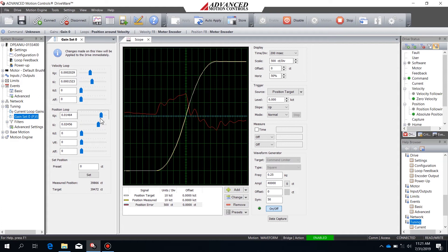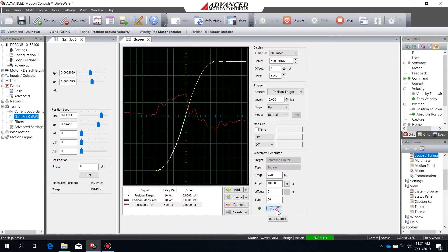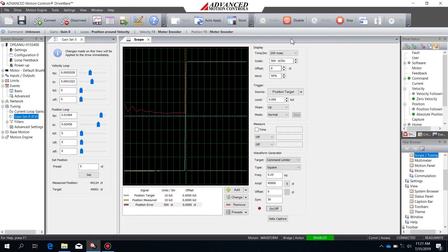Now that the error in my system is reduced to an acceptable level, I'm going to stop tuning. If you're going to continue, you might look at continuing to increase the proportional gain. If you're getting overshoot near the ends of your motion profile and it's getting unstable at zero velocity, you can begin adding derivative gain as well. For myself, I'm going to stop here and move on to position around current tuning.